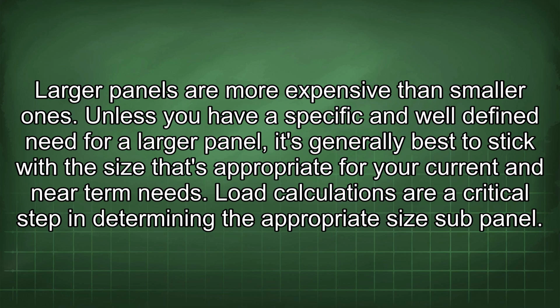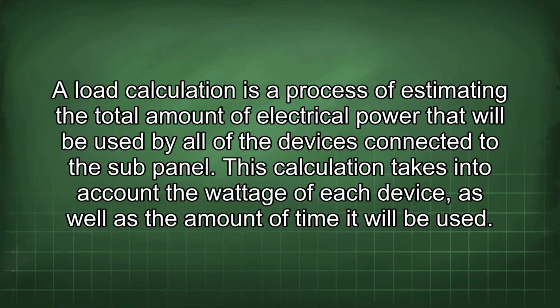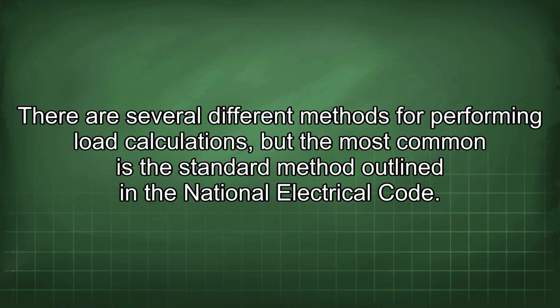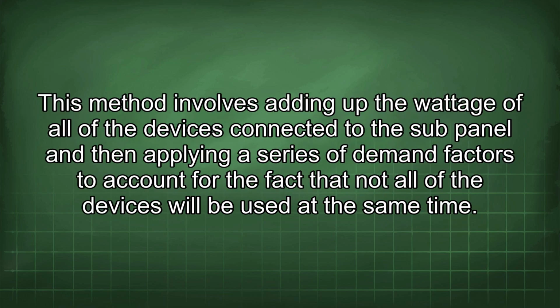Load calculations are a critical step in determining the appropriate size sub-panel. A load calculation is a process of estimating the total amount of electrical power that will be used by all of the devices connected to the sub-panel. This calculation takes into account the wattage of each device, as well as the amount of time it will be used. There are several different methods for performing load calculations, but the most common is the standard method outlined in the National Electrical Code. This method involves adding up the wattage of all of the devices connected to the sub-panel and then applying a series of demand factors to account for the fact that not all of the devices will be used at the same time.